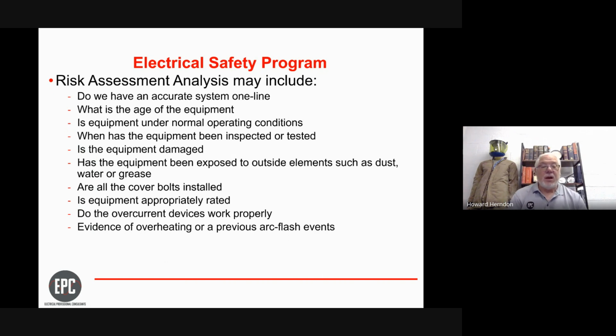Little things, like, are all the bolt covers installed? Unless you're related to electrical equipment, you may not know that most electrical covers have bolted covers, with anywhere between 6 and 15 bolts. When tested at UL and at the factory, they try to make sure those covers stay in place in case of an explosion inside that equipment.